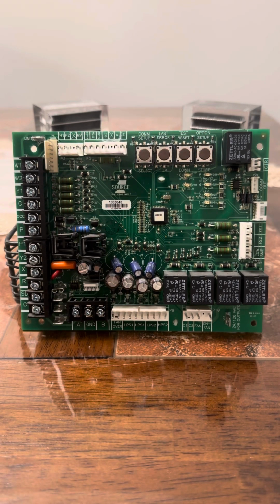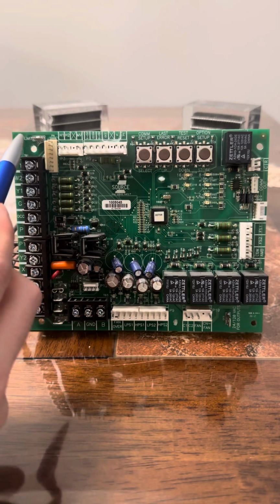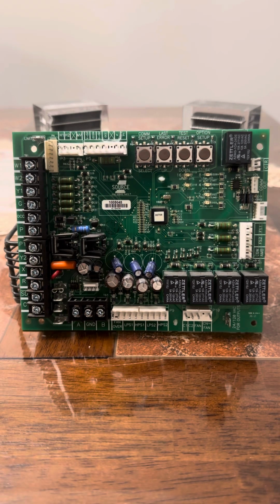Another reason why this could be happening with this 9 flash code is, if you have a 208, 230 volt unit, that transformer tap can significantly impact your voltage drop on this terminal right here. Even if the voltage drops to about maybe 18, 19 volts, it'll probably still count as 1 trip. Okay, so you definitely should double check your low voltage transformer, the high voltage tap from 240 and 208. Make sure you're tapped into the right tap. That'll definitely impact it. Corroded limit terminals, corroded wires will definitely cause a voltage drop.